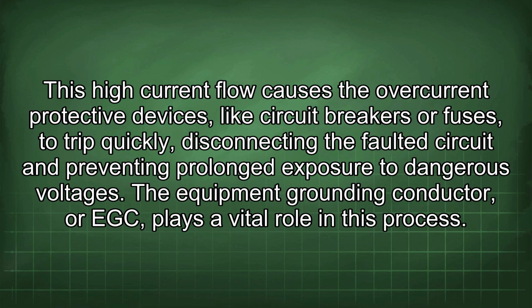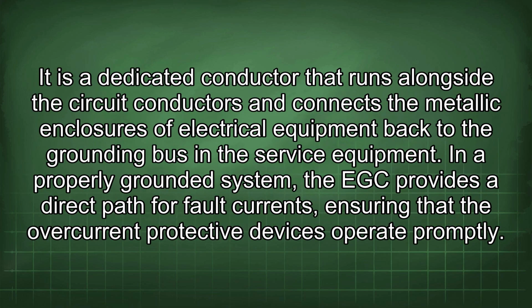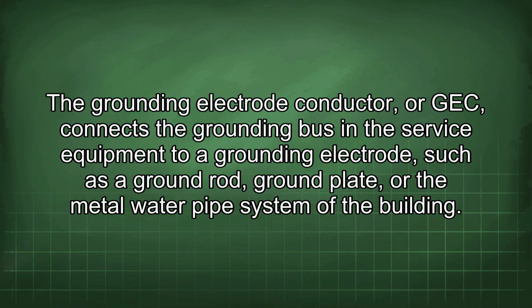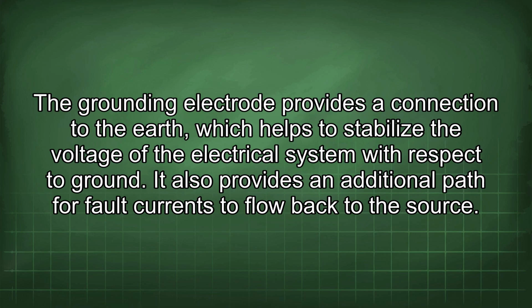The equipment grounding conductor, or EGC, plays a vital role in this process. It is a dedicated conductor that runs alongside the circuit conductors and connects the metallic enclosures of electrical equipment back to the grounding bus in the service equipment. In a properly grounded system, the EGC provides a direct path for fault currents, ensuring that the overcurrent protective devices operate promptly. The grounding electrode conductor, or GEC, connects the grounding bus in the service equipment to a grounding electrode, such as a ground rod, ground plate, or the metal water pipe system of the building. The grounding electrode provides a connection to the earth, which helps to stabilize the voltage of the electrical system with respect to ground. It also provides an additional path for fault currents to flow back to the source.